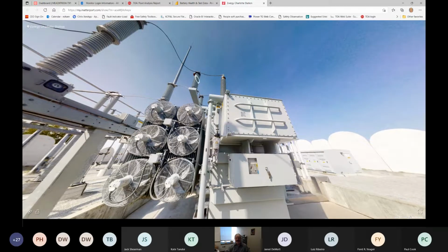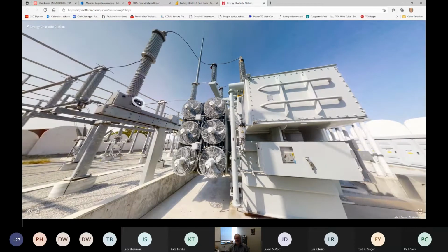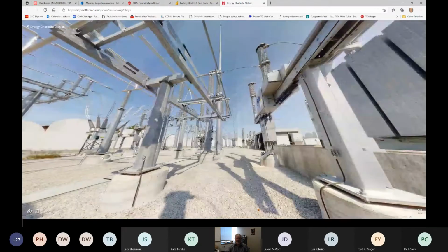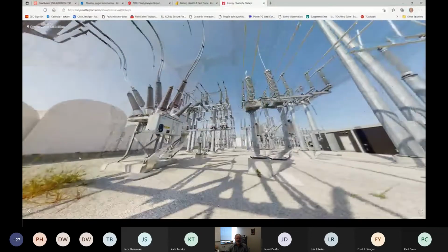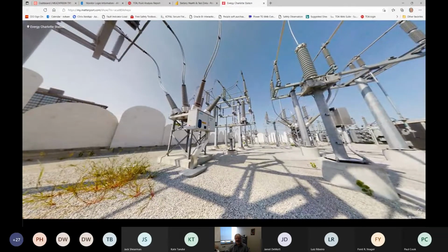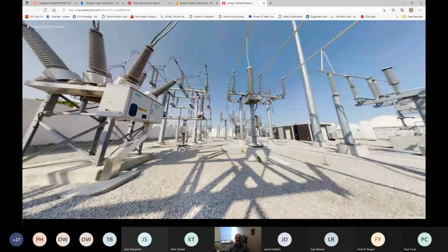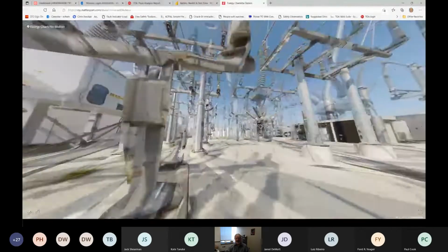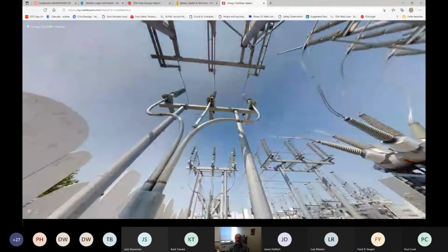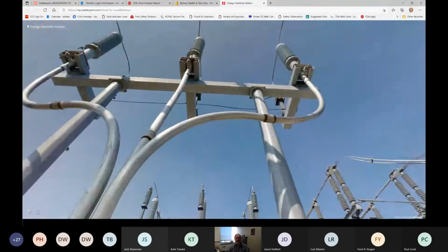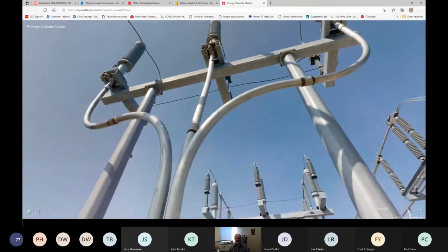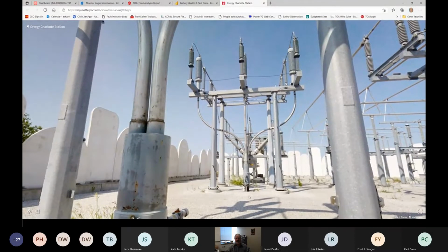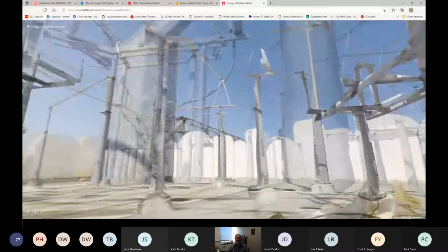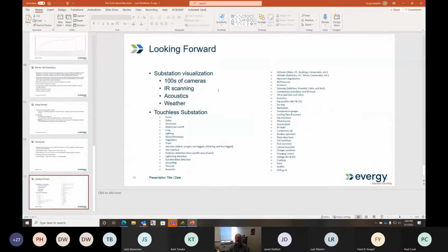Being able to see the thermal of an arrestor, the SF6 of a gauge, check and see again if we have vegetation growing in our station, and if we need to get our vegetation management out there. Let's say we have some potheads here for underground cable - we want to see if any of that's leaking. No, that all looks good. Let's look at this one over here - we can take a peek at that and see what's going on.